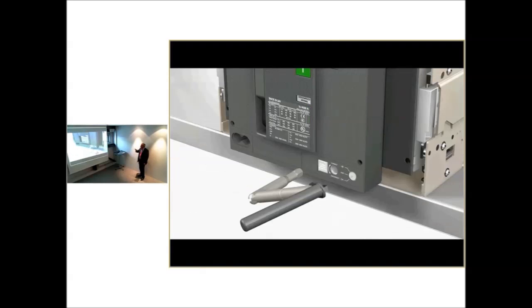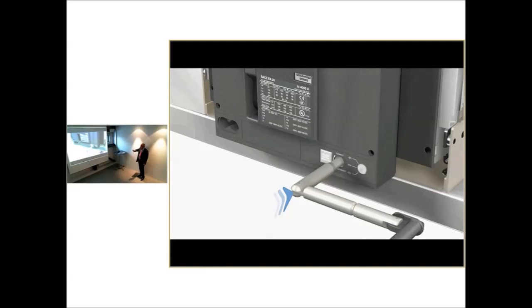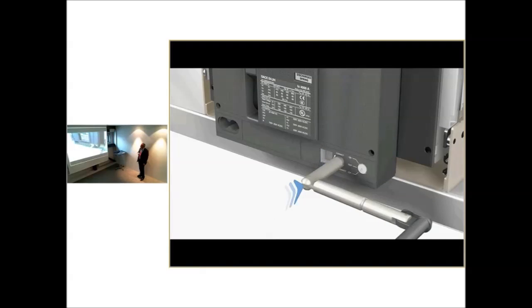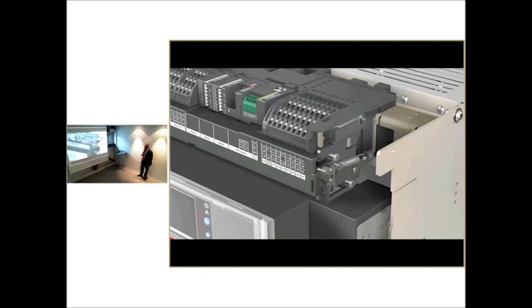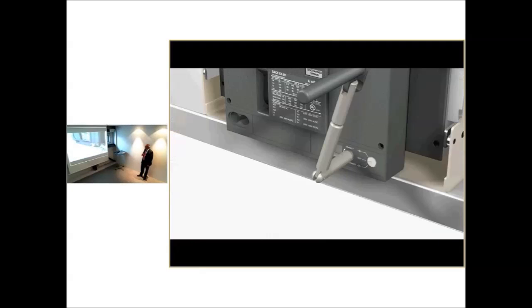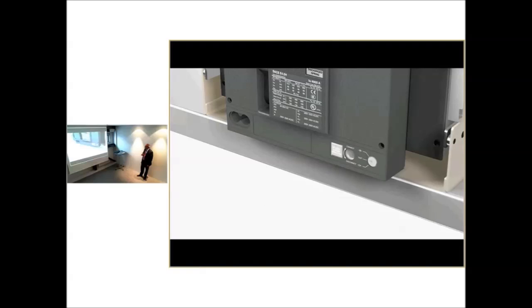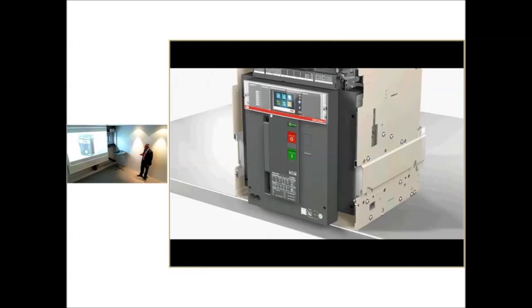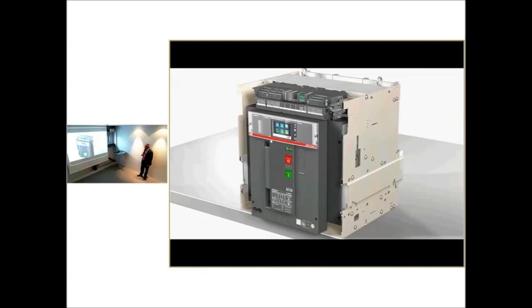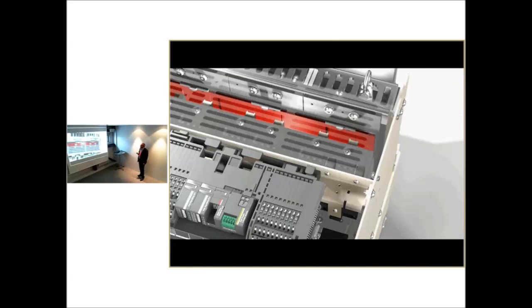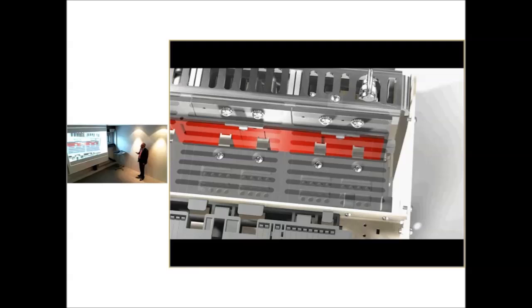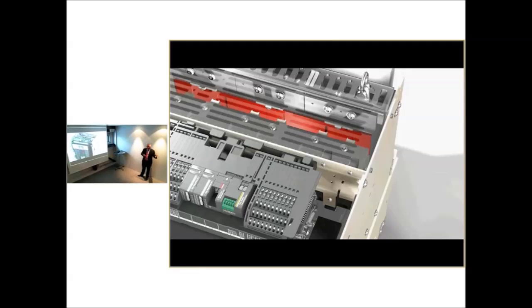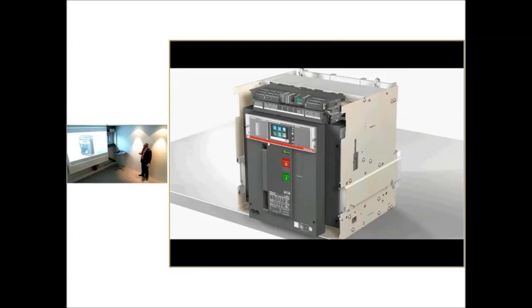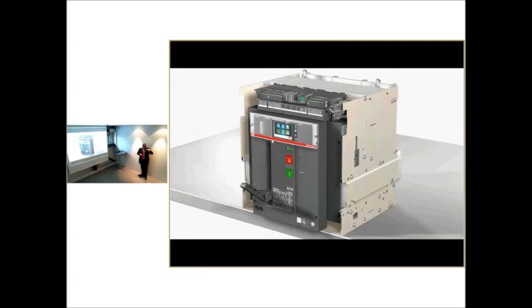Okay, push the button first. Now you can insert the handle. You are in the test position now. You see the middle position. In this position, the safety shutters are completely closed. What does it mean? You can make all the operations inside the breaker without any problems, because the live part is totally insulated.